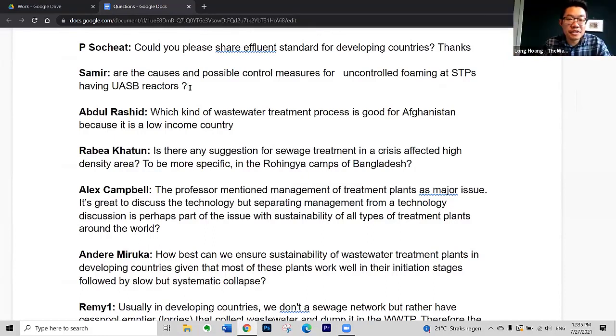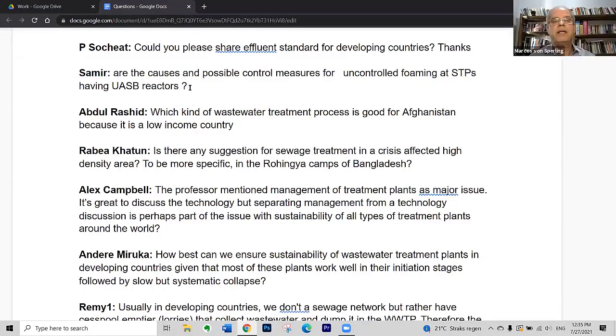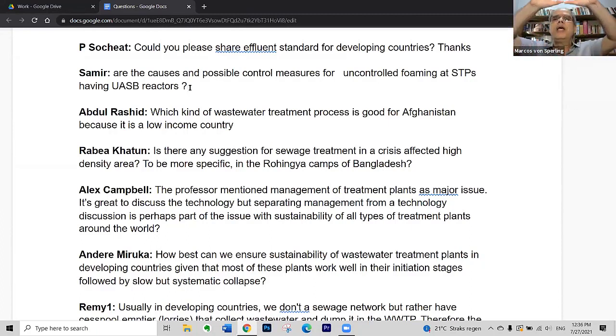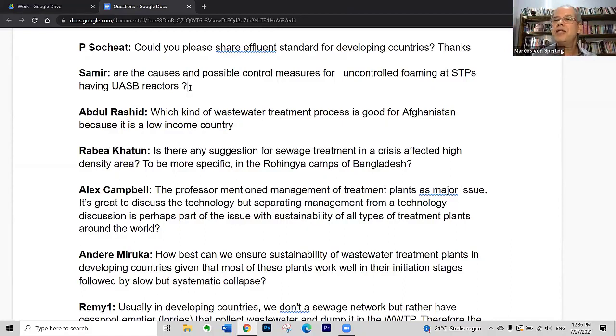The next question is from Samir, who is facing problems with uncontrolled foaming at STPs in the UASB reactors. What are the causes and possible control measures? UASB reactors — we could think in terms of scum formation, which is bacterial growth together with some fats and grease which float and tend to cover the upper part of UASB reactors. Foaming also relates to detergents and tensioactive agents. For detergent removal, anaerobic processes are not efficient — you need an aerobic stage in order to achieve foam removal from detergents and tensioactive agents.